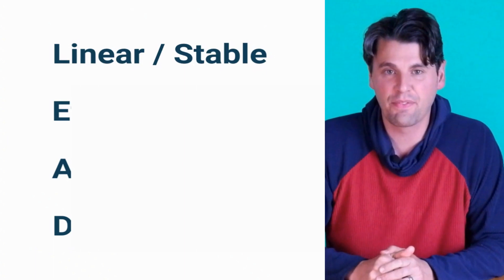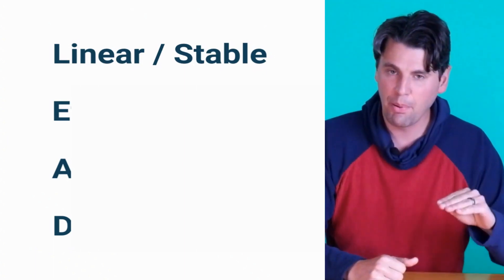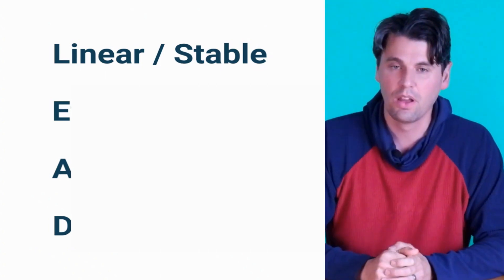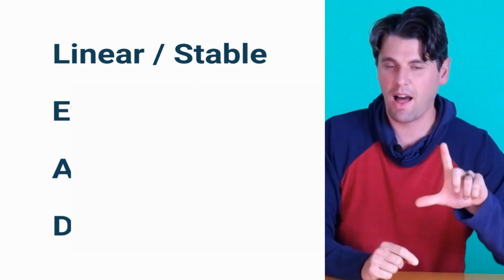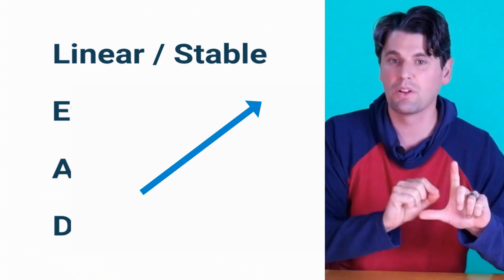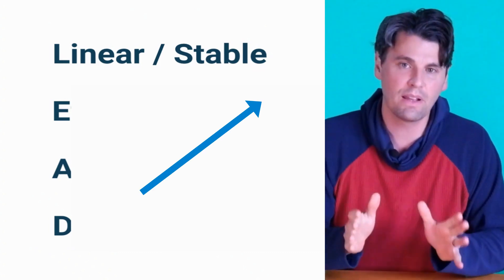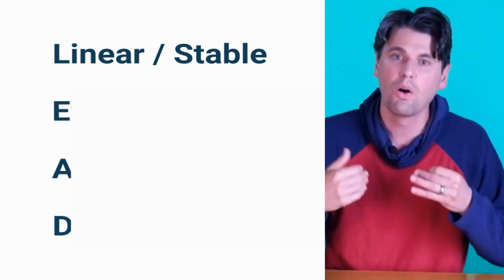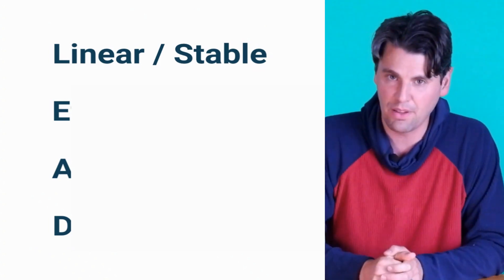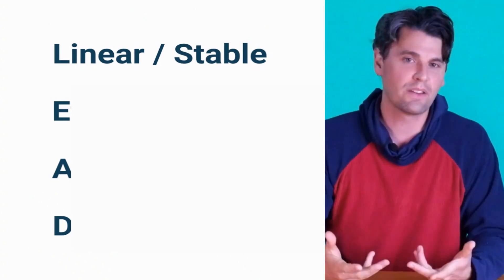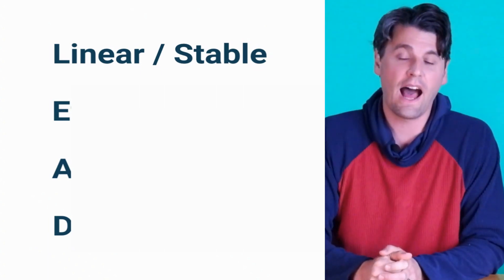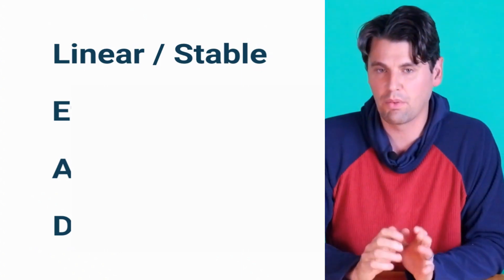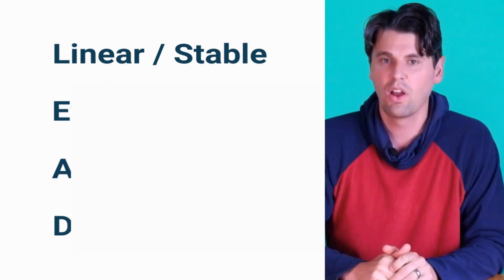Linearity is a fancy way of saying if my input goes up by a factor of two, my output will also go up by a factor of two — a straight line on an input-versus-output plot. If we deposit twice as much x-ray energy in our detector, we'd like the signal we get out to be twice as much. We don't want the signal to saturate, where at a higher level the signal goes flat or down. So linearity is number one.